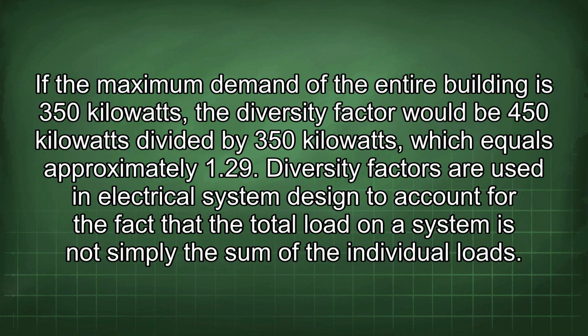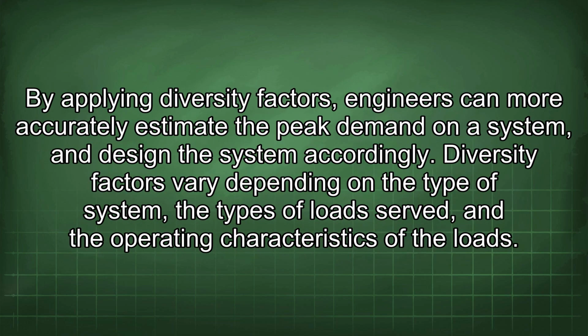Diversity factors are used in electrical system design to account for the fact that the total load on a system is not simply the sum of the individual loads. By applying diversity factors, engineers can more accurately estimate the peak demand on a system and design the system accordingly.